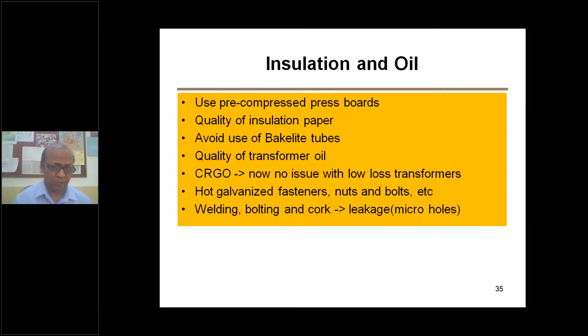The next point is hot galvanized fasteners, nuts and bolts. Yes, they must be hot galvanized. Leakage in a distribution transformer is one important parameter. Leakage near the bolts is because of cold galvanized fasteners being used. You must use hot galvanized fasteners. Cold galvanized fasteners should not be used. This is the reason for leakage. Another cause of oil leakage is poor welding, where micro holes are left.